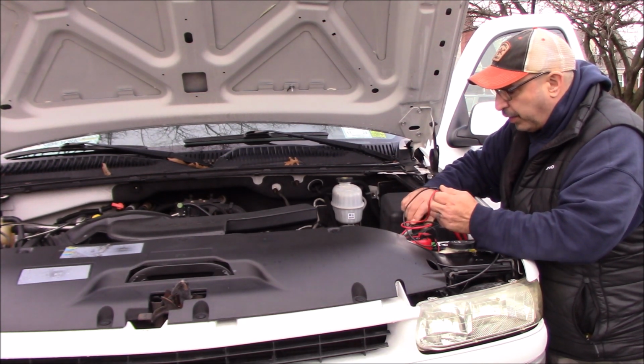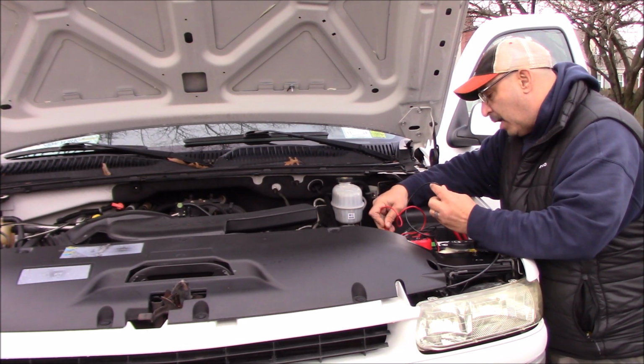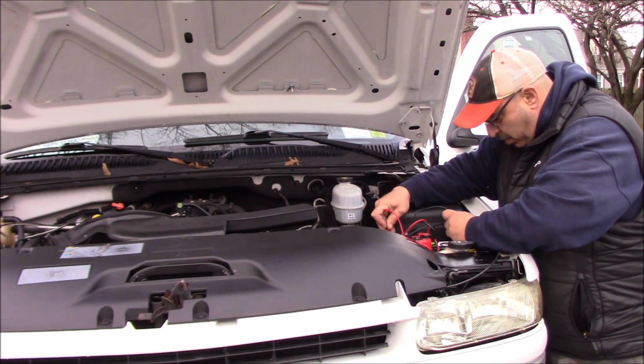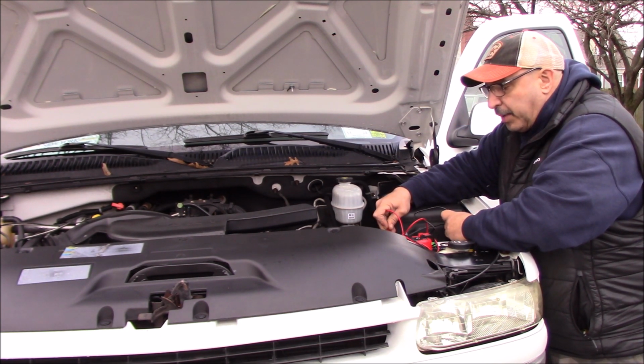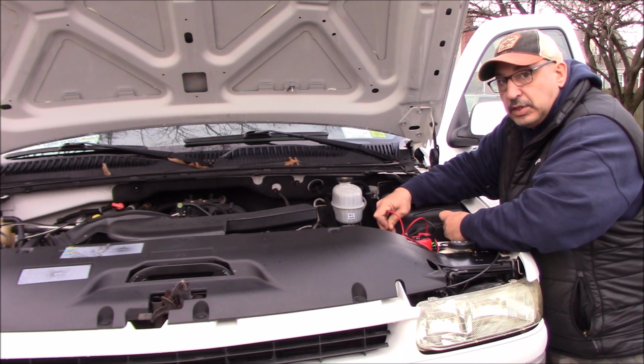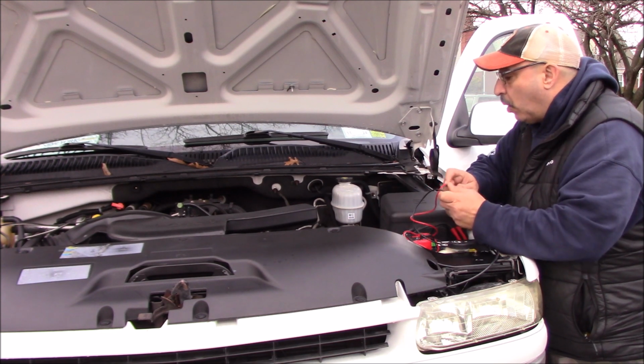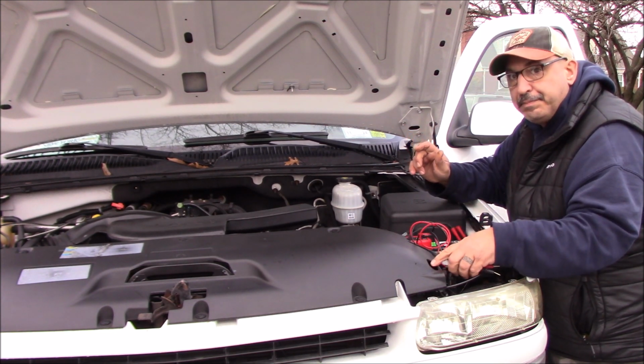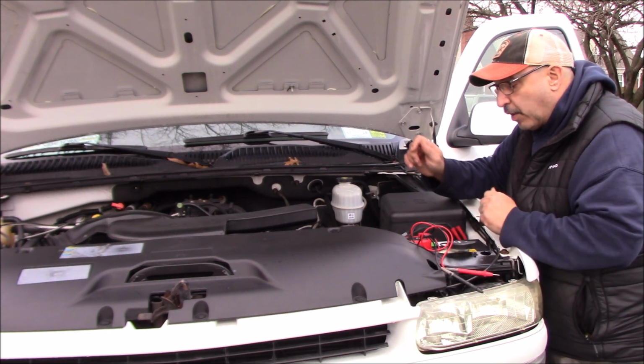I'm going to disconnect one leg of the battery charger and go to my terminals. I'm at 11.73, 72, 70 — it's just dropping. 69, 68, 67. You see how fast it's dropping. So I have a problem, and I need to figure out what it is.